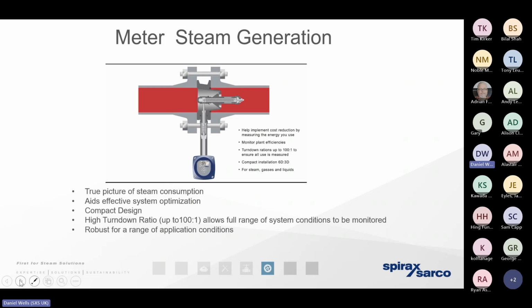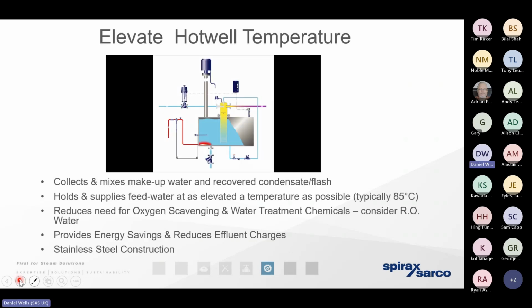We can only prove that if we're metering. So moving forwards, one of the next quick wins is ensuring that we've got high temperature hot water there on demand for whenever the steam boiler needs to respond and produce steam. We need to keep that hot well at a nice high temperature, ideally around about 85 degrees. We can't hold it at a higher temperature for reasons we've mentioned in those previous presentations. It's down to the fact that if we've got hot water at a temperature that is way in excess of 85 degrees, we're likely to get cavitation and failure of electrical components such as the boiler feed pumps.